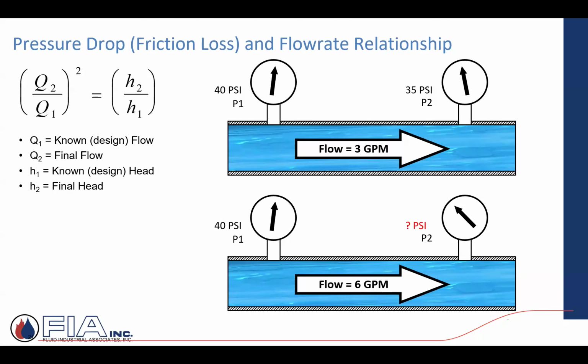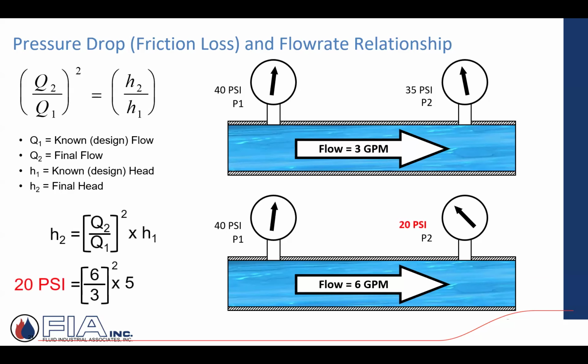So I double the flow in this case. I say, 40 PSI coming in. I've increased my flow rate to 6. What's the pressure drop? Well, my known flow was 3. My new flow is 6. 6 divided by 3 is 2. 2 squared is 4. 4 times my original 5-pound pressure drop. I'm going to experience a 20-pound pressure drop through that same coil if I try to double the flow rate. Something to be aware of.